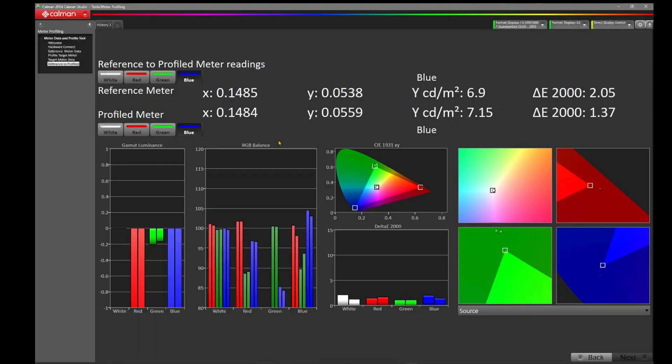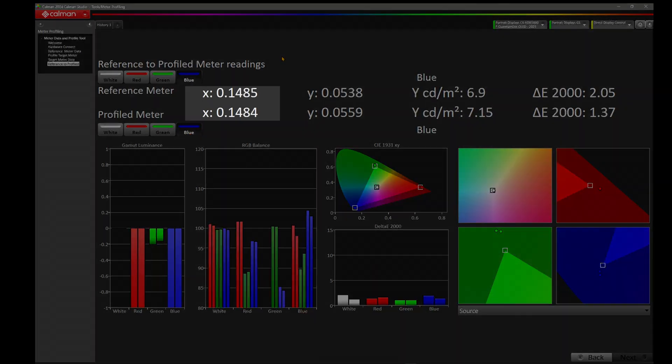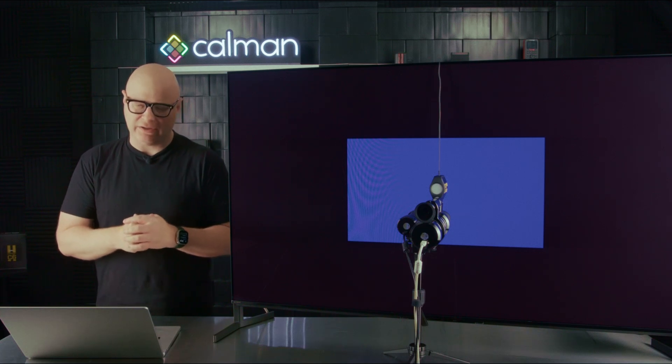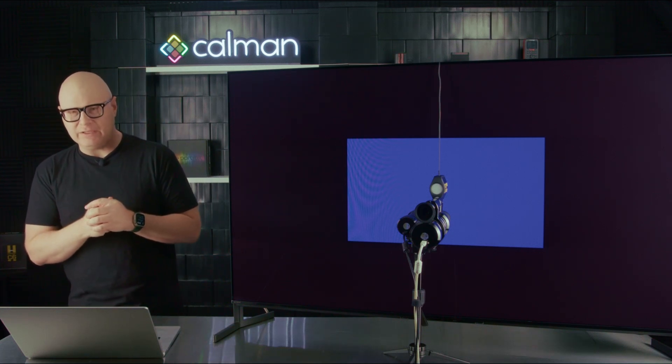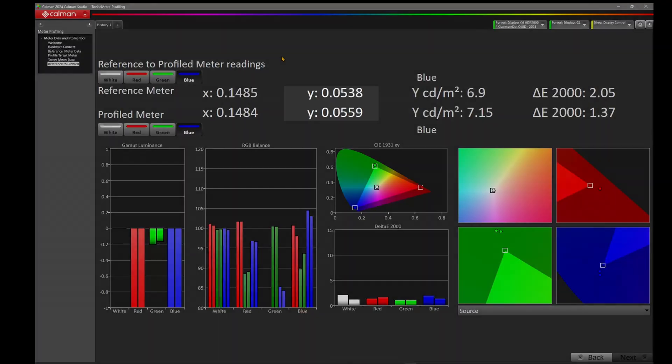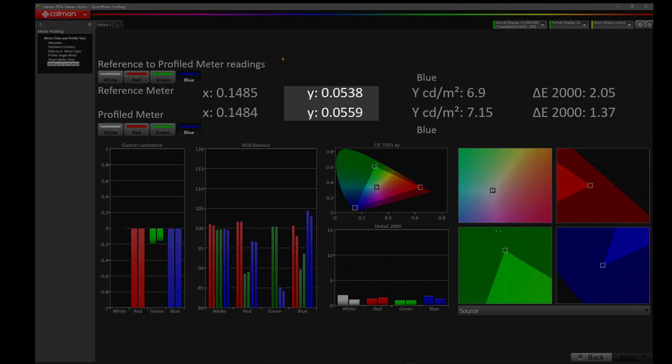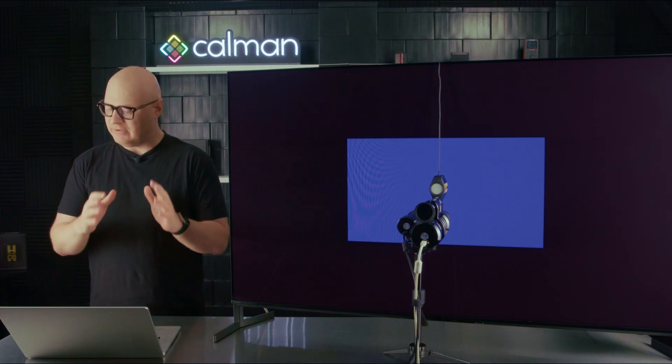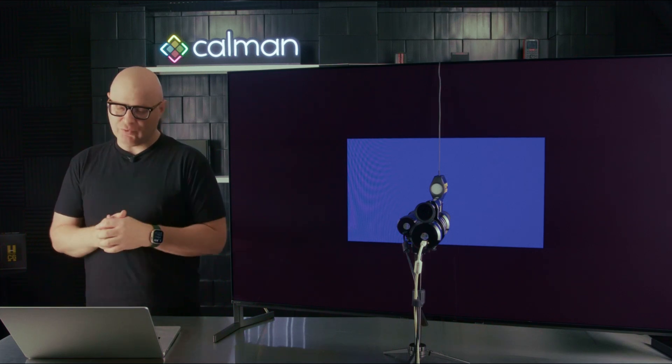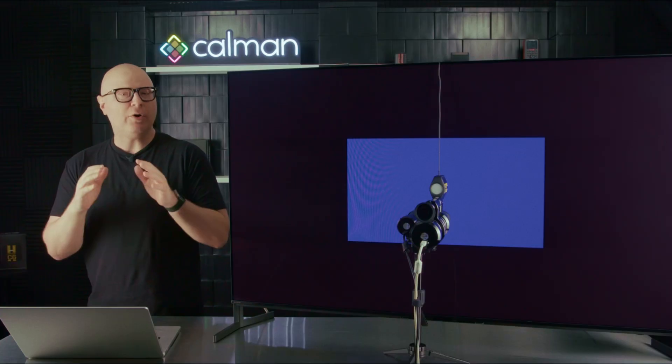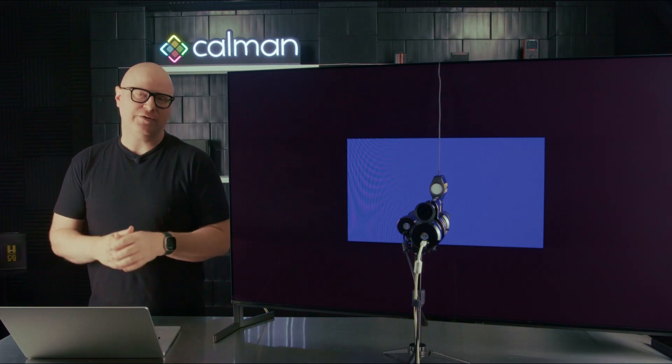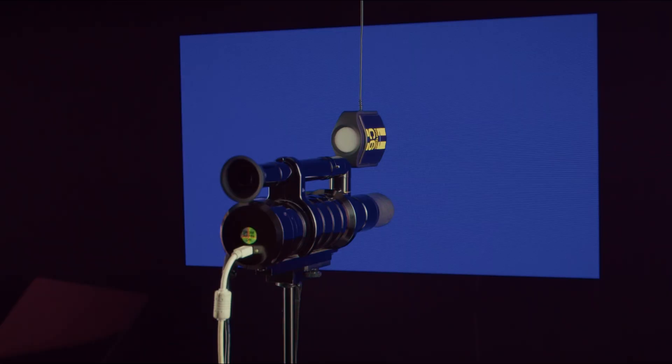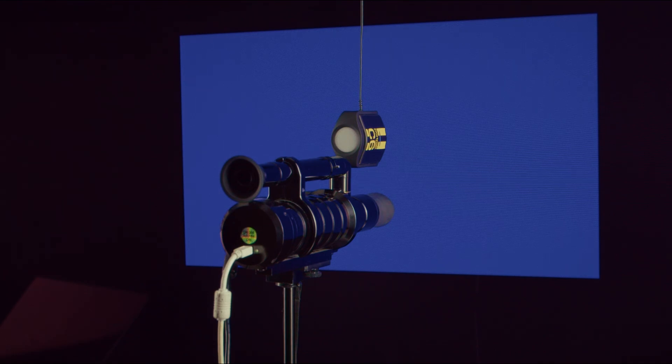Lastly, let's now take a look at blue. We're going to click on blue in that top left corner. We're going to go down and change the C6 HDR5000 to blue. And let's take a look at that X. 0.1485 and 0.1484, a difference of 0.0001. Very close. This is well within meter repeatability of both meters and what we would expect to see. Looking at Y at 0.0538 and Y at 0.0559, it's about a difference of 0.0021. And looking at that large Y, we've got a nit level of 6.9 on the CR300 and 7.15 on the C6 HDR5000, a difference of about 0.25 nits. Both meters measuring very close, well within the repeatability expectations of the CR300.